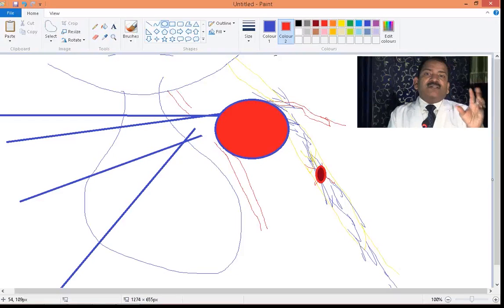So the first way is to hold the minimum amount of tissue at one time. Second, you hold the minimum intensity of current at one time. And third, you do intermittent activation. Intermittent means stop, open, stop, open. And when you are removing it, the surrounding cold tissue will make your tissue colder. That way you can minimize remote injury.